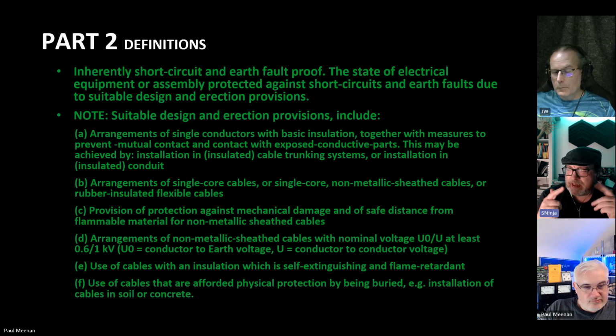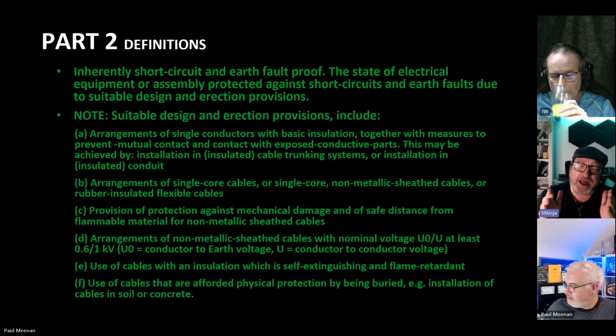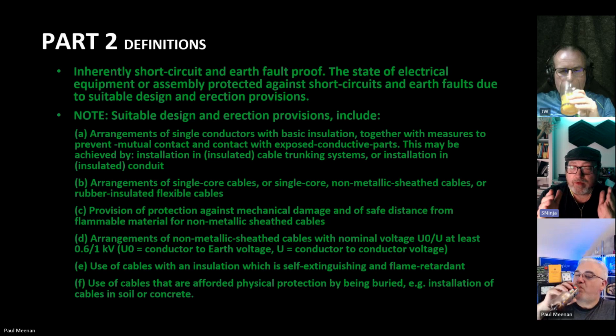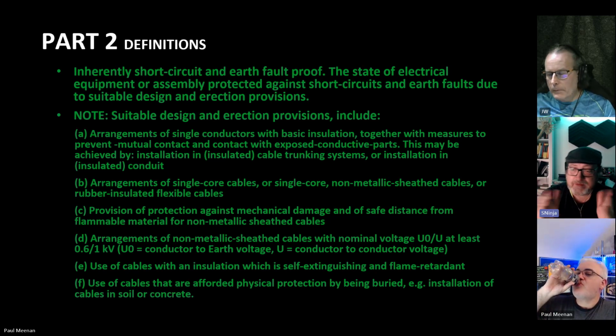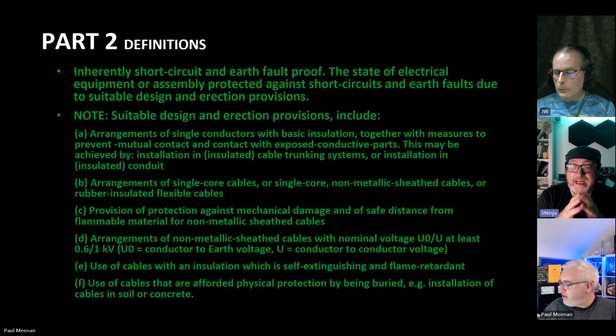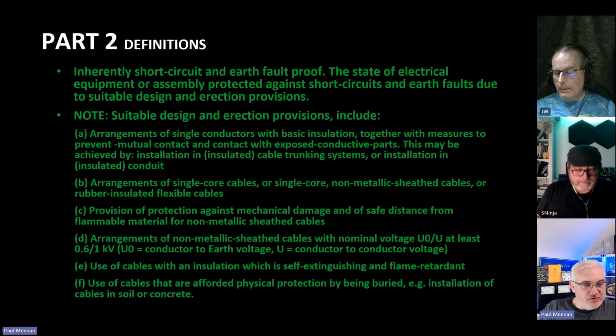Yeah, this just screams, in the current version of 7671, when we talk about segregation of systems, band 1, band 2, then we look at SELV and PELV and isolating SELV from PELV and SELV from SELV and SELV from earth. We just basically say put it in an insulated system, either an insulated sheathing or insulated containment, insulate the system, and that looks like what this is, but obviously at installation mains level. Well, the definition part E: use of cables with an insulation which is self-extinguishing and flame retardant gets my vote. Keep that bit, please. We shouldn't be using PVC cables anymore. 2024, we've got to stop. Yeah, I think we can move on.